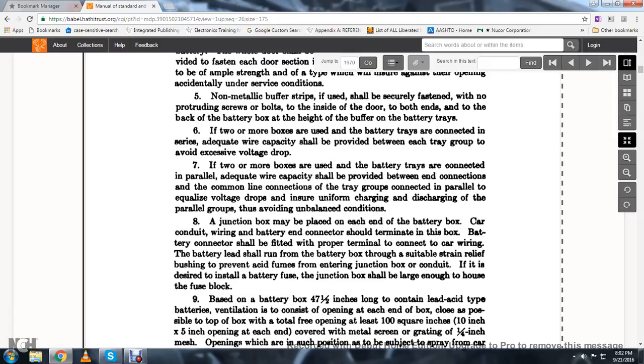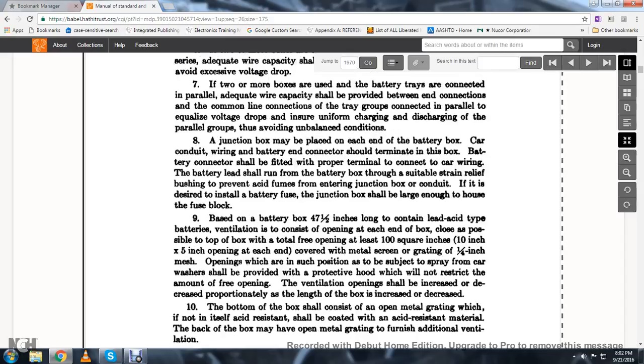If two or more boxes are used with the battery trays connected in parallel, adequate wire capacity should be provided between connections of the common line connections of the tray groups connected in parallel, to equalize the voltage drop and ensure uniform charging and discharging of the parallel groups, avoiding unbalanced conditions.